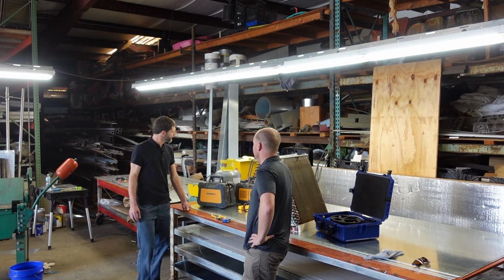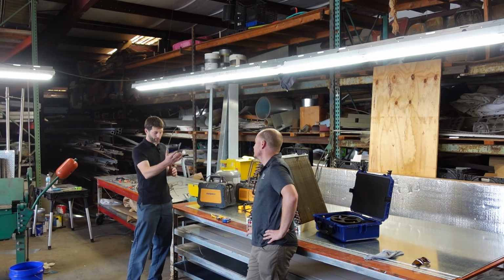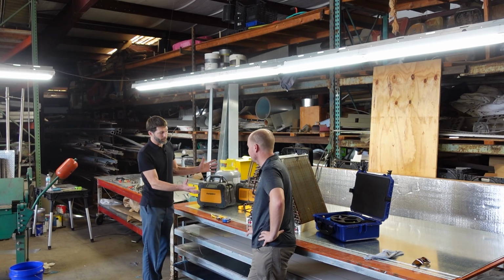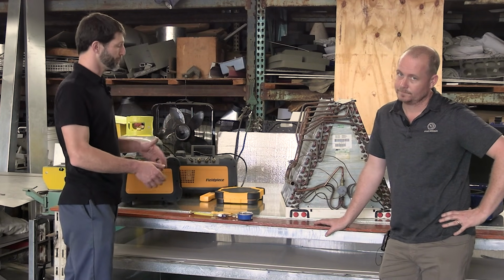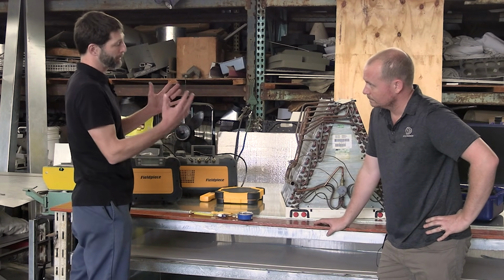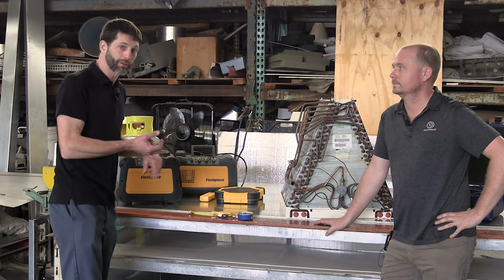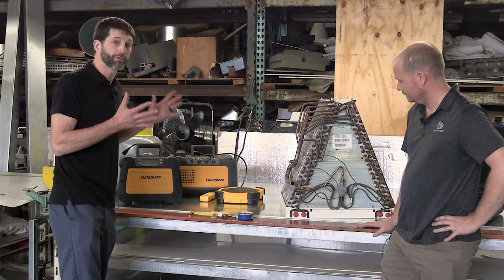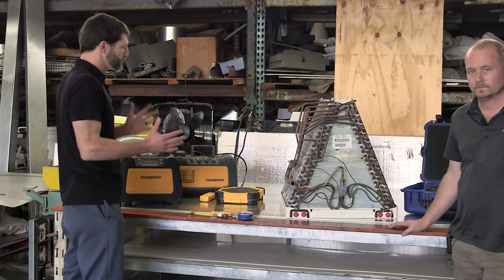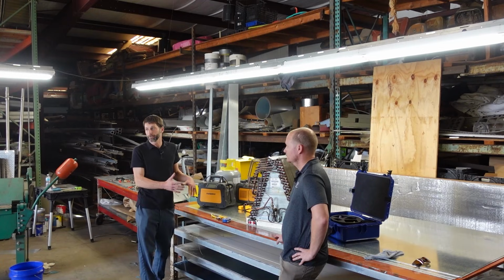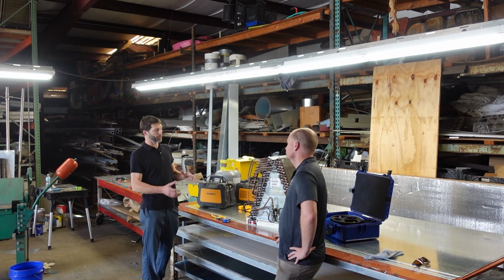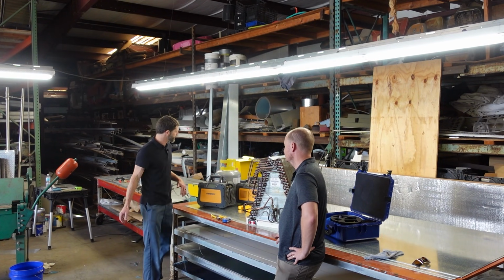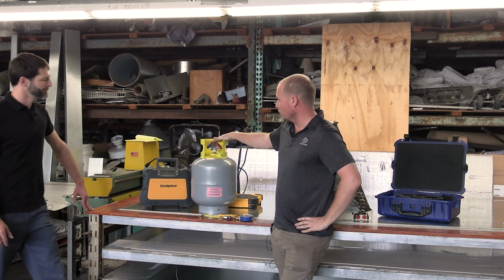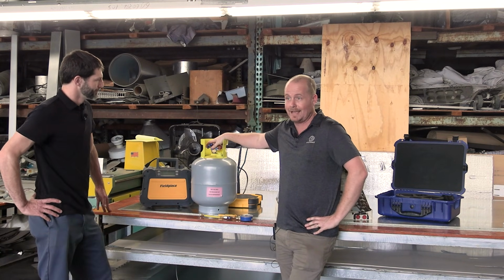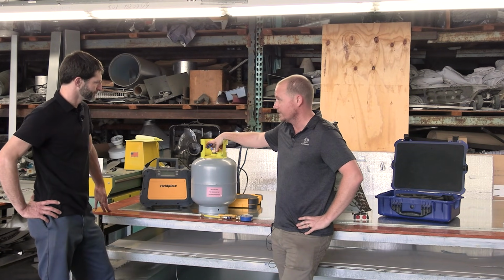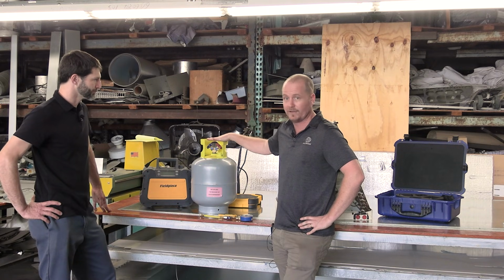Yeah, absolutely. And to Brian's point, you do a lot of work working on the system. So you're recovering the refrigerant, you're replacing a component, maybe it's a filter dryer, maybe it's a TXV or some other component within a system. You're doing all that work, so why would you put the old refrigerant back in there again? You want to take that from a virgin bottle whenever possible, so that's definitely what you want to do. So when you're working with a recovery bottle that is empty and you're going to put some refrigerant in it and you know there's nothing in it whatsoever, you need to pull a vacuum on it first.